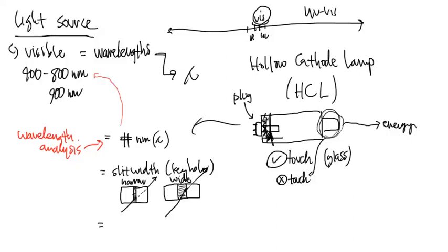All right? So you've got to dial in the wavelength, and you have to dial in on the slit width. The other piece that's on the label that's pretty important is the recommended voltage. And sometimes they'll do milliamps. It really depends on the lamp manufacturer.